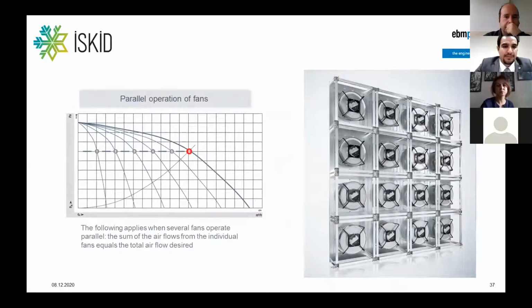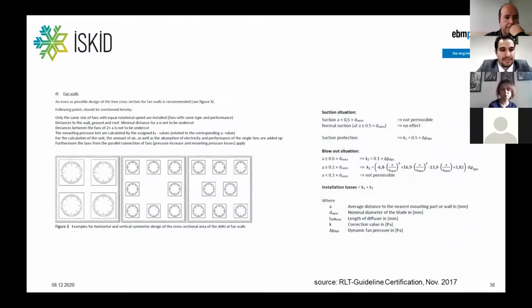When it comes to parallel operation of the fans, this is also more and more popular to overcome tasks or jobs with high airflow. You know that each fan is adding up the flow. So if you have one fan, you have one flow. If you have 10 fans, you have 10 times the flow. And therefore it needs also some rules. That's why there are also definitions about how to position the fans inside a unit. It is said it must be a horizontal and vertical symmetric design. And then the same formulas as mentioned before occur. And so each fan is considered to be a single fan with a certain space.